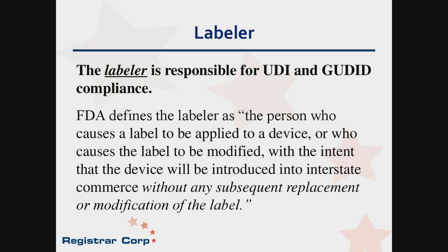That most likely means, in simpler words, that if you're the brand owner and your company name is on the label, most likely you are the labeler and you are responsible for the UDI requirements. Even if you are maybe not the manufacturer of the device, but the label of the device states your company, it's your brand name, then you are responsible for the UDI regulation.